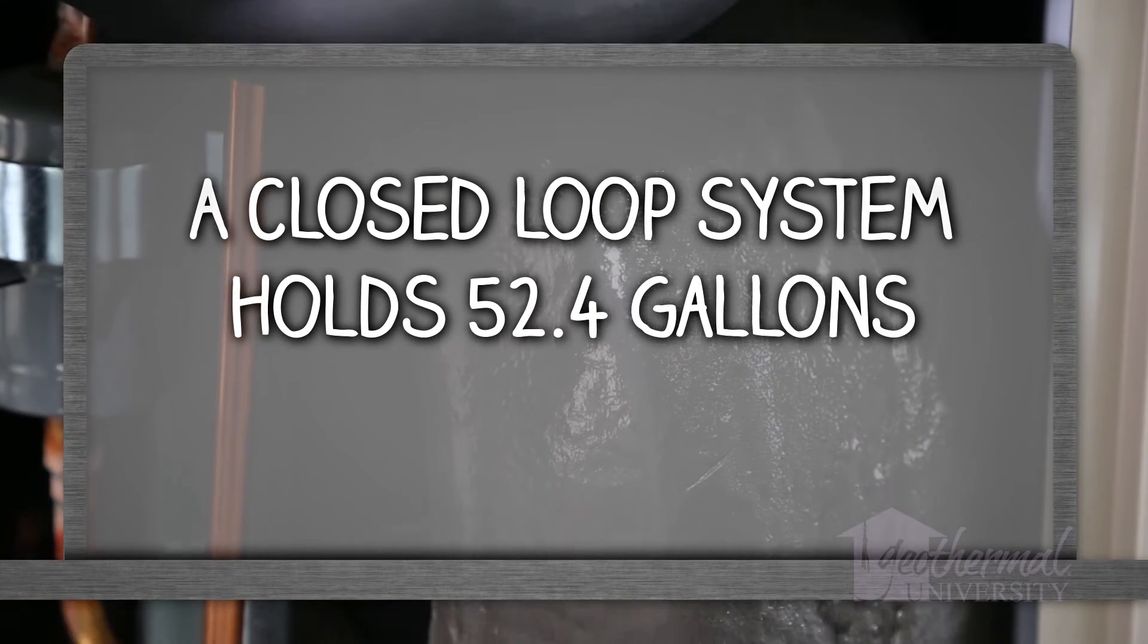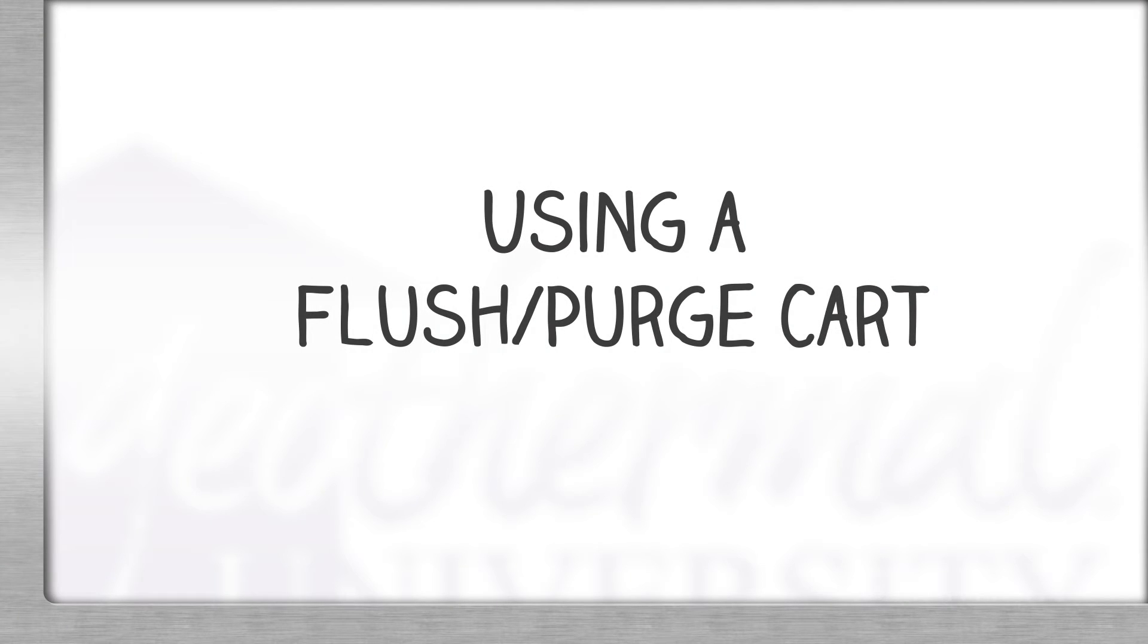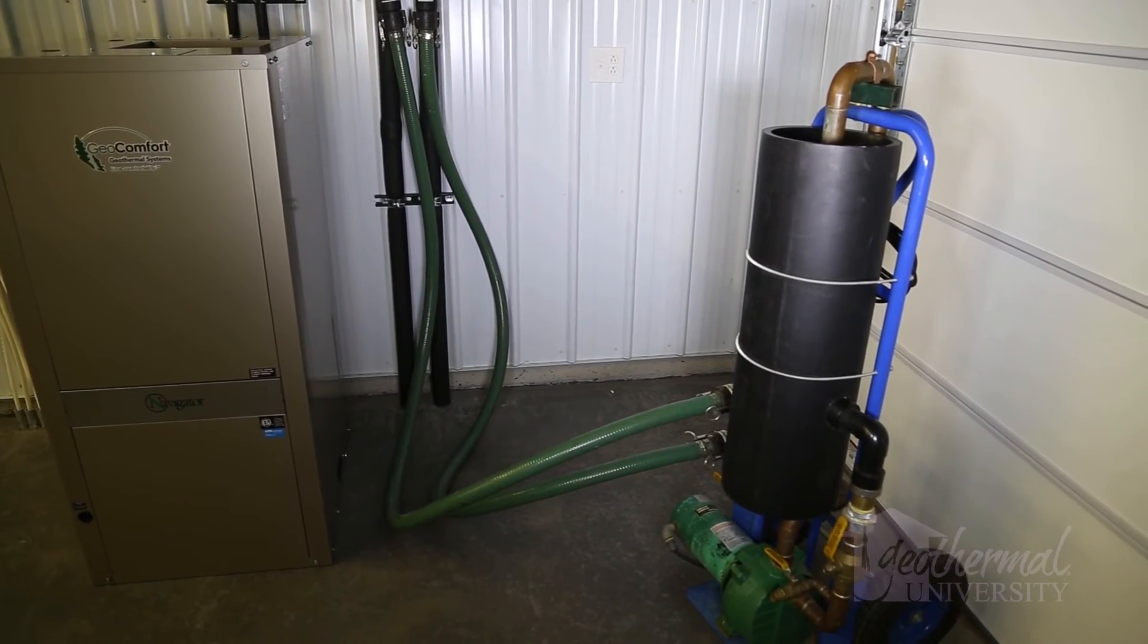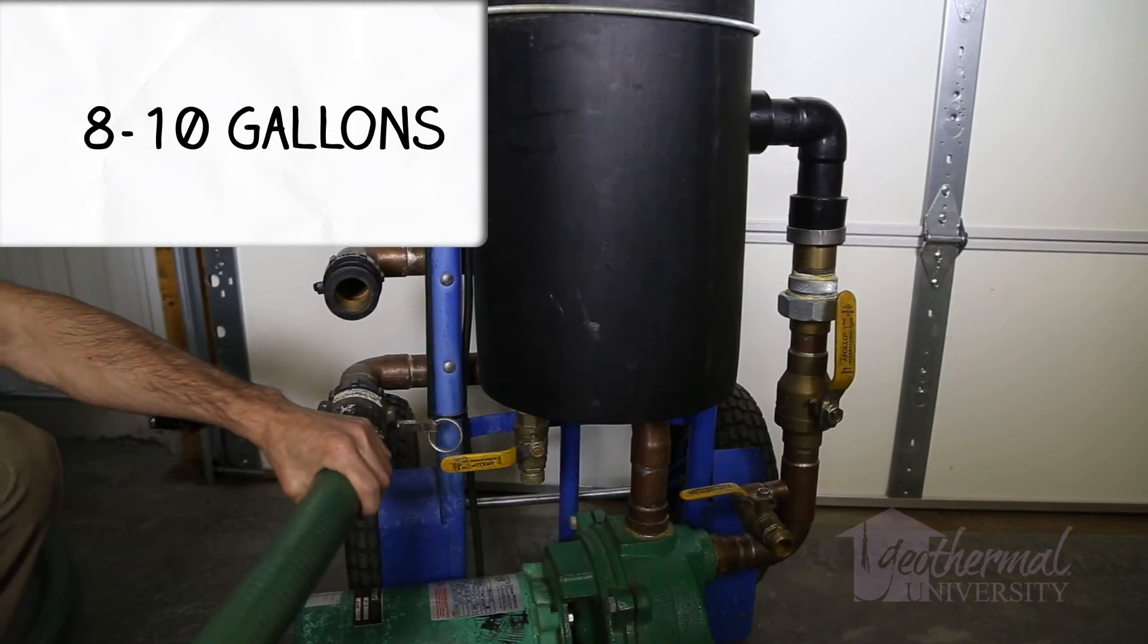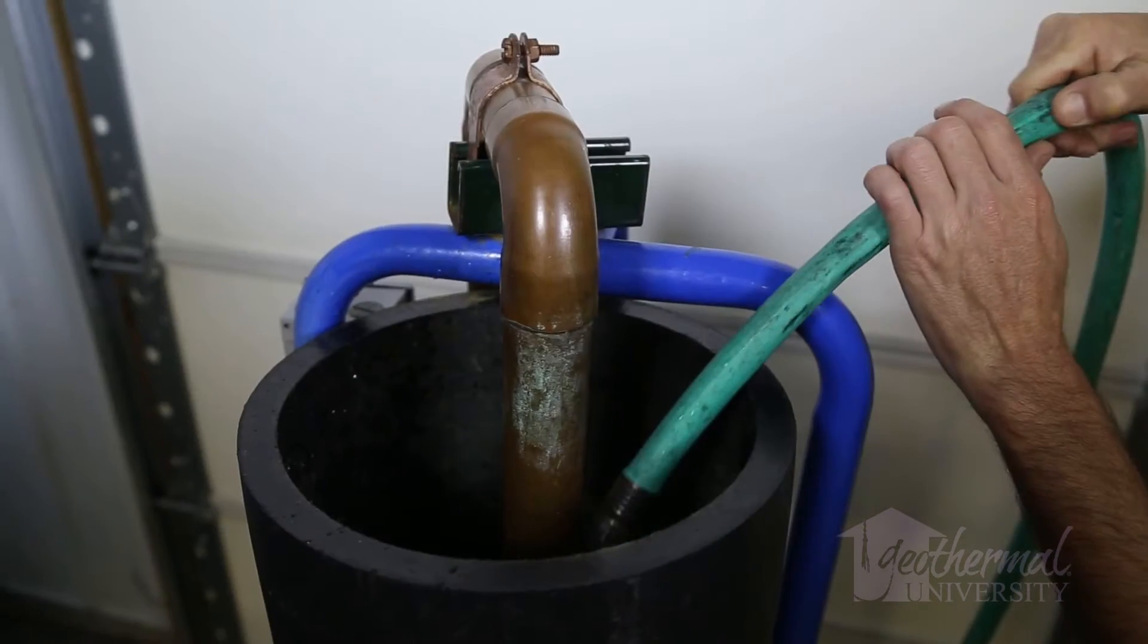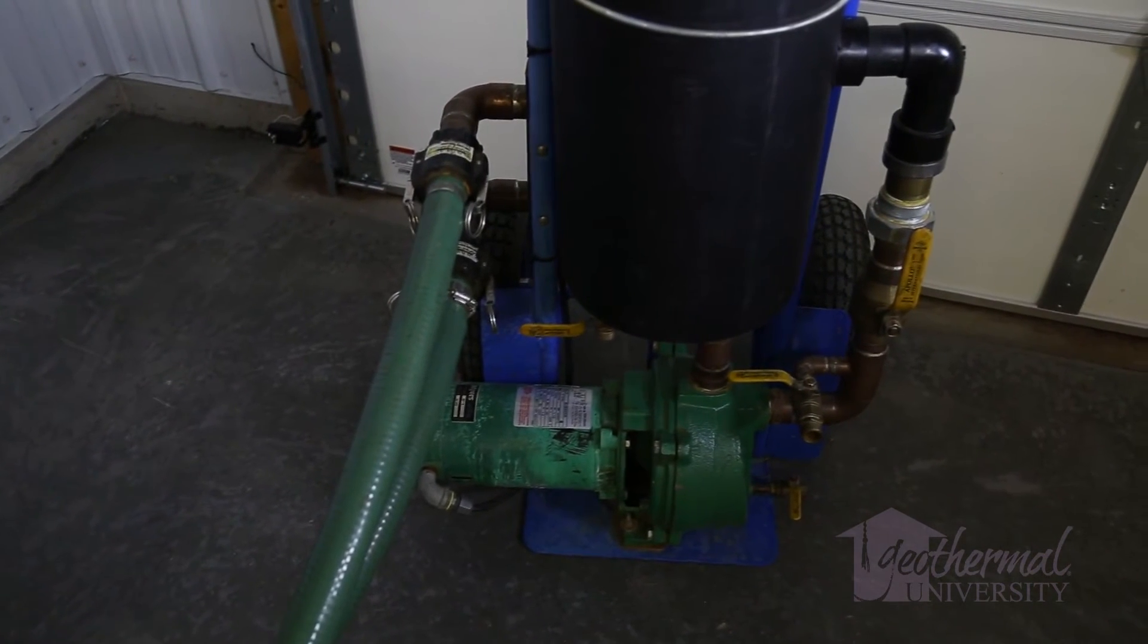Our geothermal closed-loop system holds 52.4 gallons. If you are going to use a flush purge cart, one last component may need to be added to our calculation. A typical flush cart holds about 8 to 10 gallons. To calculate the correct amount of antifreeze, the gallons in the flush cart must be included in our calculations and treated.